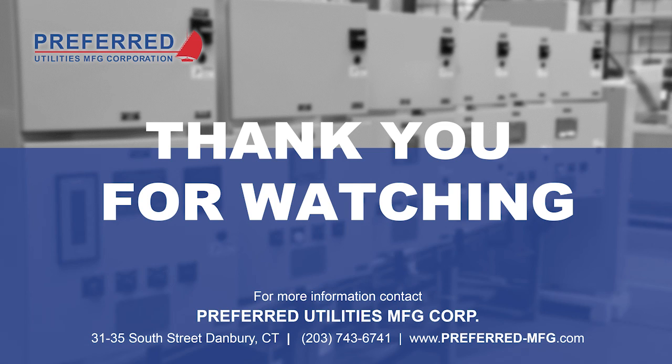The reason that we say that the supply pump has to take into account both the generator consumption and the size of your belly tanks is there was a job in Florida recently that bought someone else's fuel system, and they looked at generator consumption and they put about a 15% safety factor on their transfer piping. You know, probably just rounded up to the next size pump. And the problem was the belly tanks were 2,500 gallons apiece, and it was taking over 12 hours to top off a belly tank, and the pump was just running all the time.